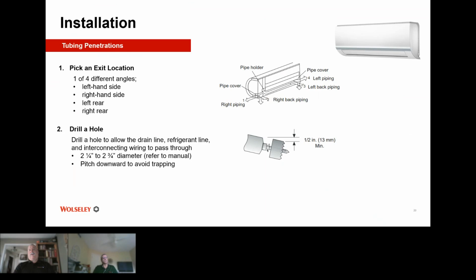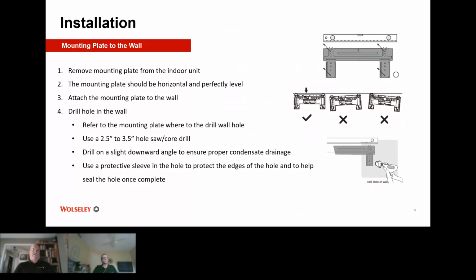Now, as Joey was talking about before, and as the presenters from LG were talking about in the previous session, mounting the plate to the wall is key. We want to make sure, first and foremost, that it is perfectly level. If we try to aim the unit to slope to the left or to the right, it's not aesthetically pleasing, and then the customer may come back to us and ask to adjust it. So please get a 2 or 3 foot level, put it on top of your mounting plate, and then mark your holes, drill them out, and anchor that back plate securely. A good looking level or plumb installation makes for a happy customer.